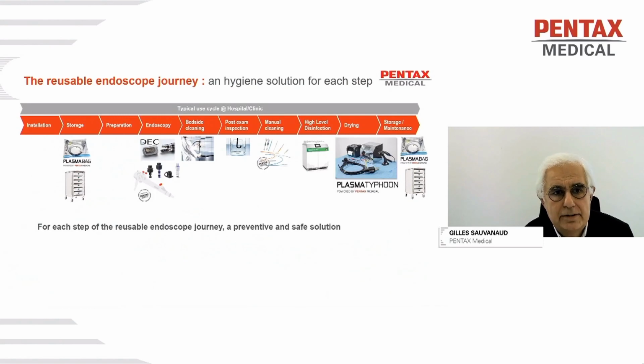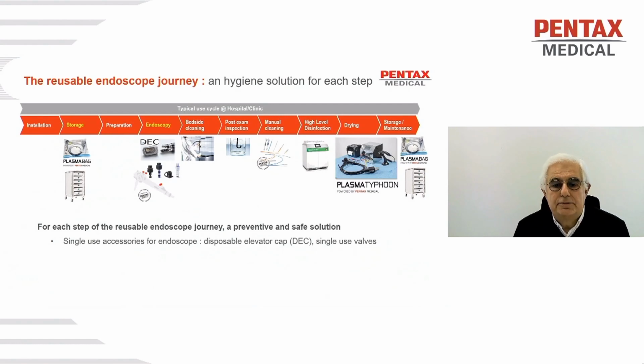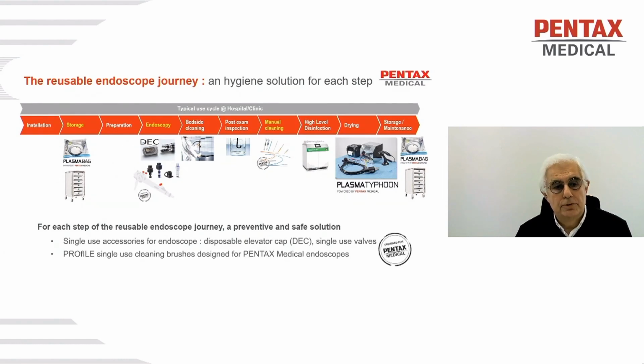Now let's look at the reusable endoscope journey, and especially the hygiene factor. At Pentax Medical, we're not here only to produce and sell endoscopes. We want, by design, by the new devices, by the solutions, by the accessories, to improve this journey and make it a safer journey. The single-use accessories for endoscopes are helping us to reduce the risk. The disposable cap and disposable elevator reduce dramatically the risk of contamination on the duodenoscope, and especially make the cleaning much easier and more efficient. The single-use valves also remove a burden from the manual cleaning. We're talking about the brushes. Having our own brushes is also helping the cleaning to be at its best.